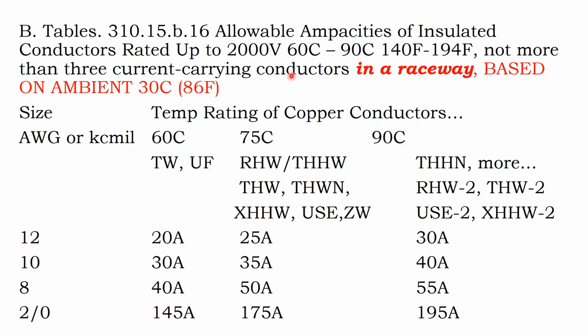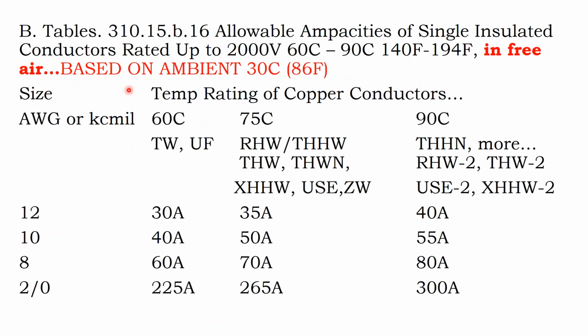The temperature of your conductors is going to vary depending on whether your conductors are enclosed in conduit versus direct burial versus hanging in free air. And so then we get into other wire sizing tables that apply to your conductors in a raceway versus in free air. We see that this is the 86 degree chart, and we're using 90C wire, and it tells us that a number 10 can handle all the way up to 40 amps. Then in free air, the same wire, number 10, can handle up to 55 amps. It's because it's cooler than if it's enclosed in a raceway.